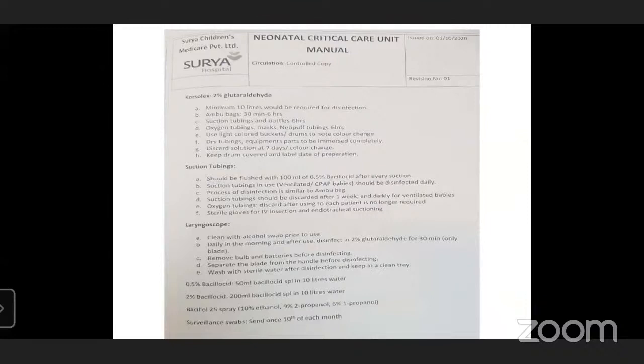The other thing is the suction - second point, third point, fourth point, yes. Point E, if you look, you need to use light colored buckets, because most of these solutions, being alkaline with bicarbonate in them, are color coded. They come in different colors, something in rose, something in light yellow. The reason is if the disinfectant efficacy comes down, this color fades. For example, if you prepare a 2% solution and it becomes dilute because of all the water on the surface of the equipment, the color dims - it becomes light pink instead of dark pink. That is why you need to use them in transparent buckets.